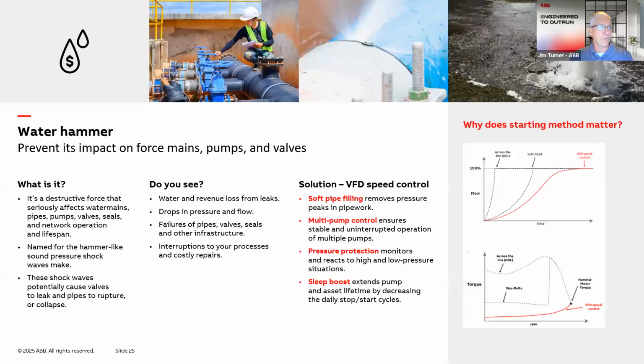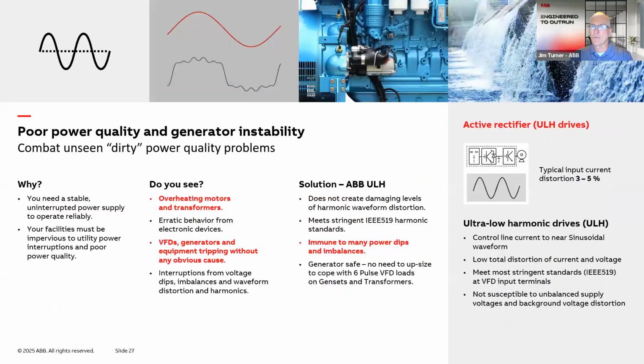Now, beyond preventing water hammer, an ABB VFD can be programmed to control multiple pumps and provide additional controls and pump protection that we have highlighted in the red text above. So let's focus on the second. Oop, went too far. Sorry about that.